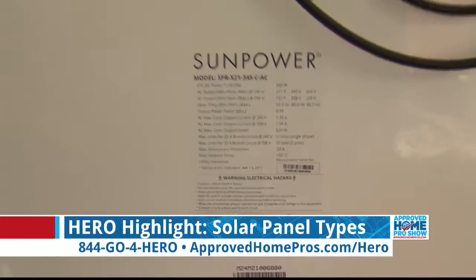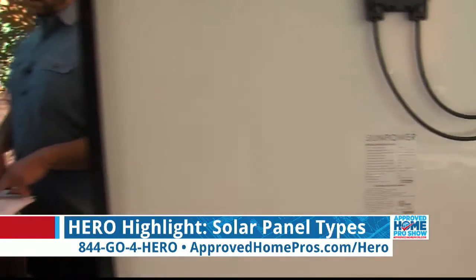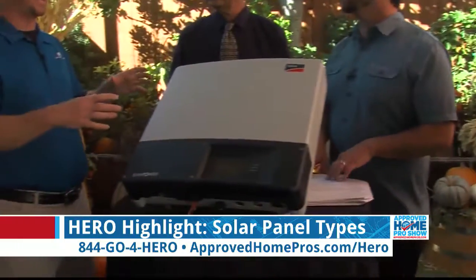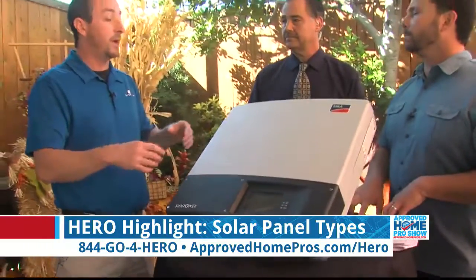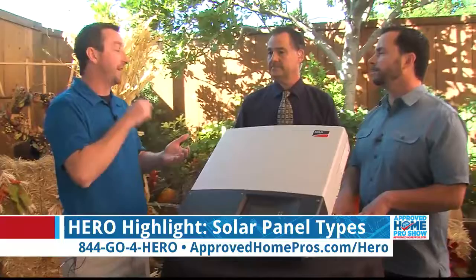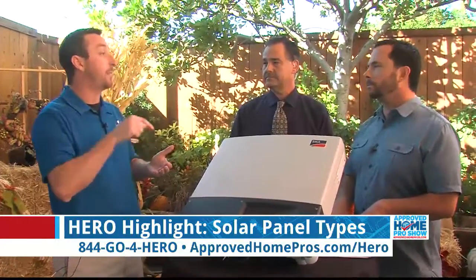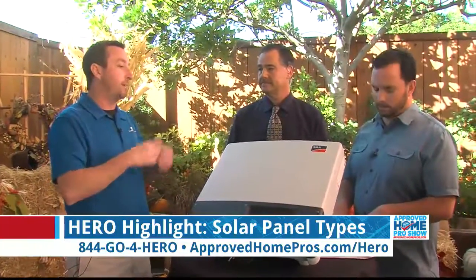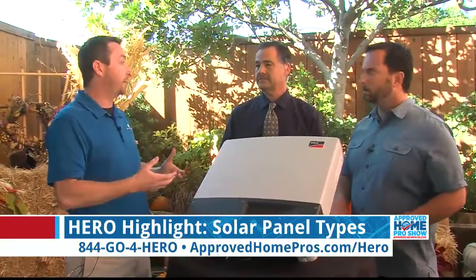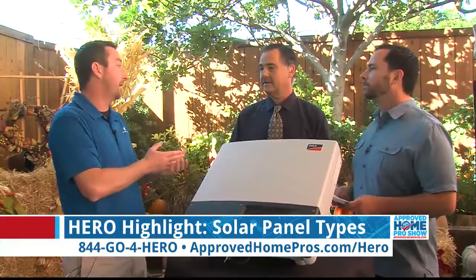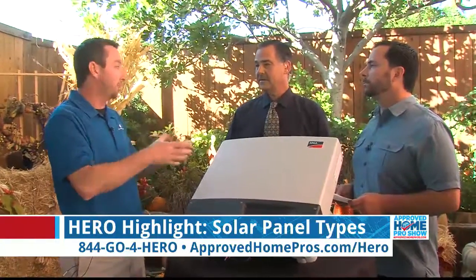With microinverters or AC PV, the difference is that in addition to all the same things that you have with a string setup, you also can see the independent output of every single panel and every single microinverter, so that if one panel goes bad or one microinverter goes bad, you can actually see it and identify it in the monitoring so that you know if there's a problem.